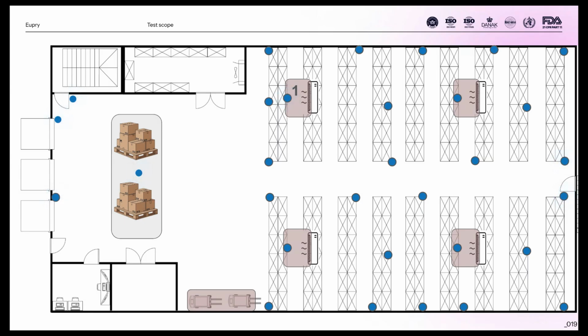It's important to understand that we should have both mapping and alarm testing, and those should be tested individually. But often, due to good planning, alarms are tested during the mapping exercise, because that's usually when you don't have sensitive goods stored yet, making it easier to test the alarm system. That said, the mapping exercise should often be followed directly by putting a monitoring system in place.